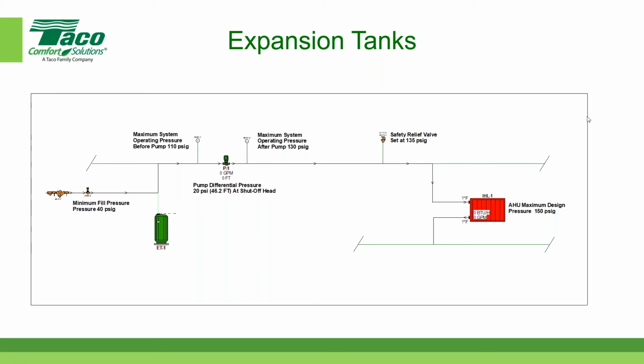So I'm going to draw in an imaginary valve. If I put a valve here on my piping system, and I put a valve over here on my piping system, let's say they were manual valves, and someone closed each one of these valves, then the maximum pressure that my system would see would be equal to the suction pressure plus the shutoff head.